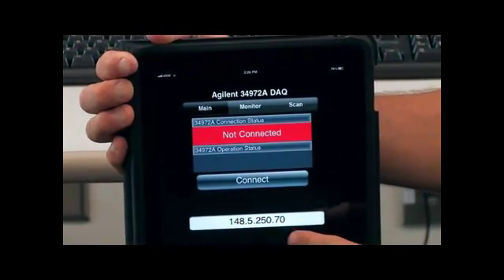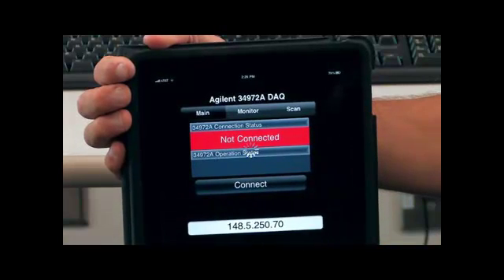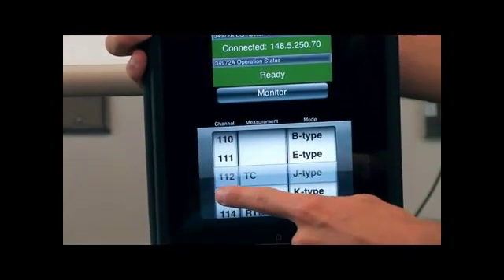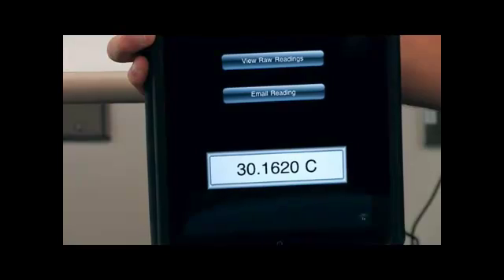I'm going to use an iPad and an iPad app that's available to anybody, free for download. It's called 34972A DAQ. I'm going to use this app to connect and make a measurement with the instrument. I already have my IP address typed in. I'm going to press connect. The connection was made. Now I'm going to monitor a channel. The thermocouple is connected to channel 112, J-type — monitor — and there's our reading.